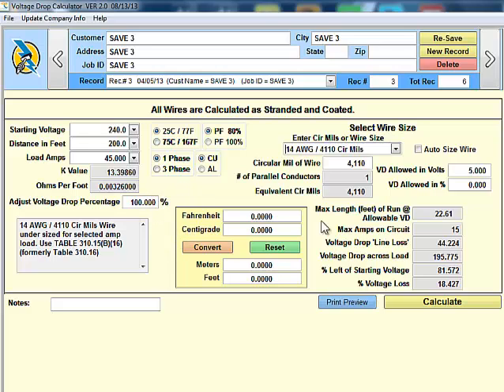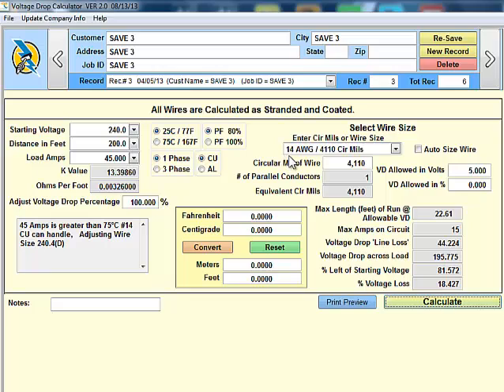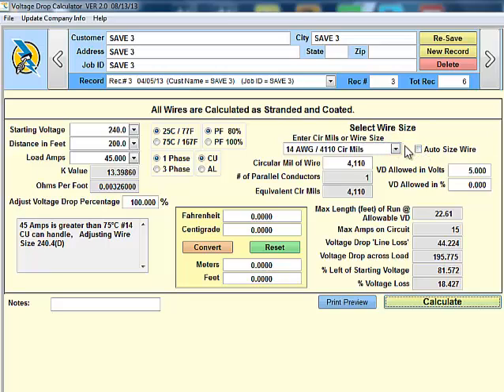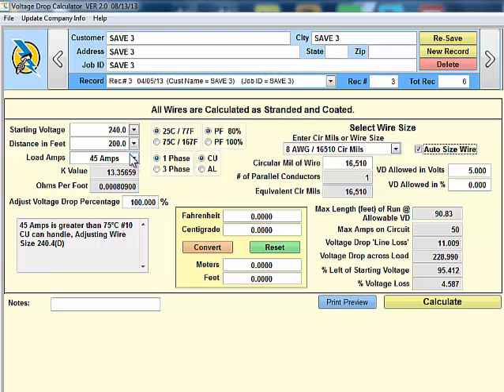Let's calculate it. To get the 45 amps, if we were using 14 gauge wire, first of all, the code does not allow you to put 45 amps on 14 gauge wire. So let's click the auto wire size. And it says we need a number 8 for 45 amps.